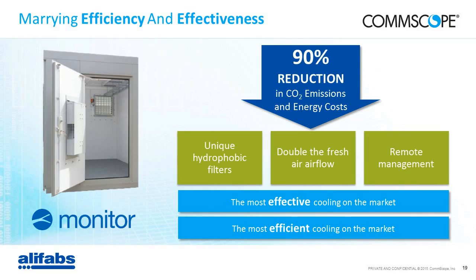Okay, so what makes us very different is because we think we found the right balance between efficiency and effectiveness. So just to give you a comparison, an air conditioning is pretty effective, but it's not always that efficient. Meanwhile, free cooling can be very efficient, but not always very effective. It will hit the ceiling of capacity pretty quickly. The reason why we're both efficient and effective is because we use hydrophobic filters, and I will go through it in a bit more detail in a few minutes.